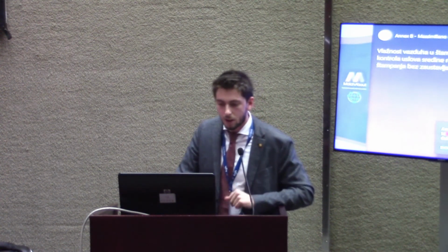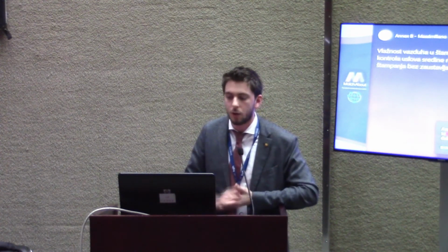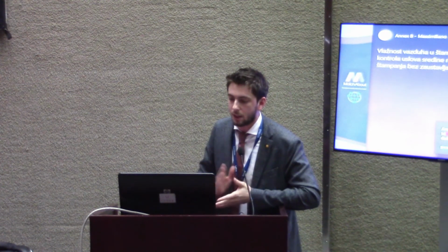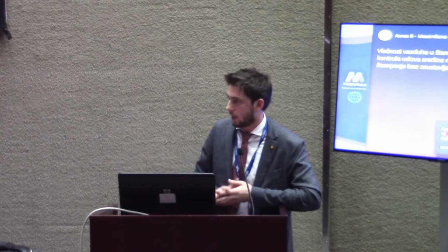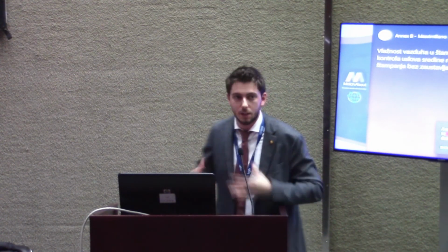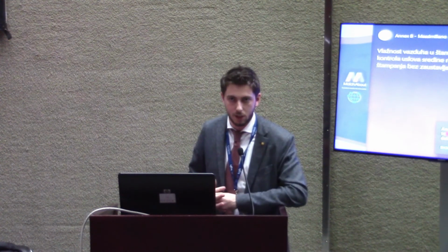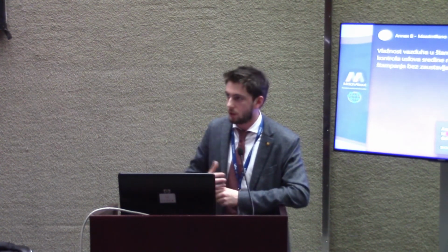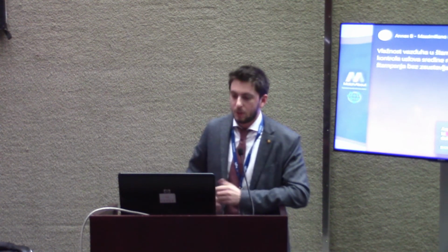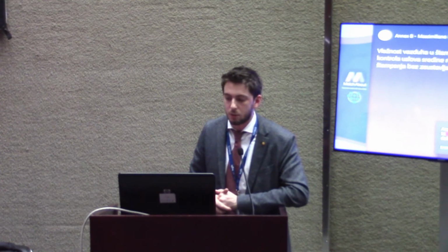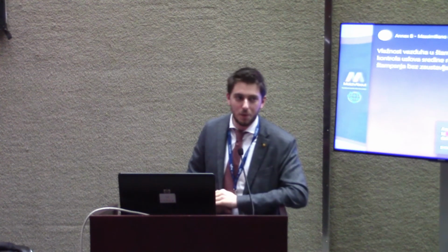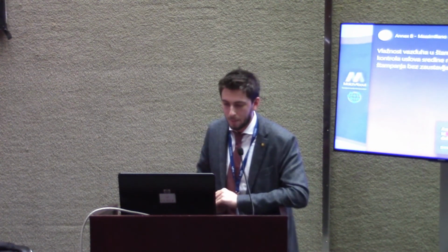Conclusions. Temperature and relative humidity must be controlled to ensure an efficient process in the printing industry. Changes in relative humidity can cause dimensional variation and other defects, as I briefly highlighted before. A humidification system should be used in printing facilities to increase the overall production efficiency and ensure the best quality results. The average set point is between 55–60% for offset printing and 50–55% for digital printing.